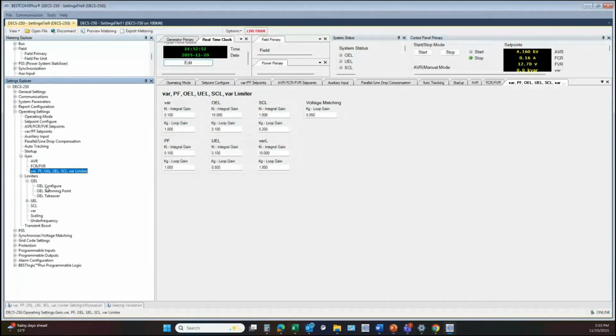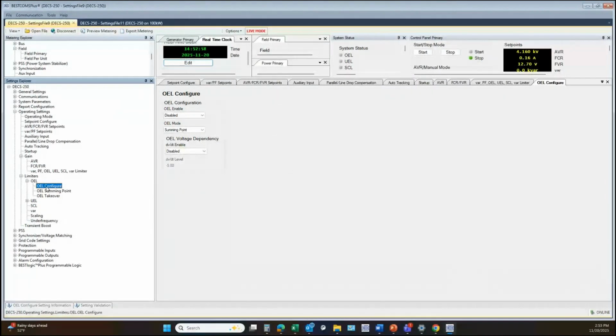Limiters are very important, especially the overexcitation limiter within the DECS. You will not have a better piece of protection in place if the DECS can control excitation directly. Then you should rely upon it to limit excitation instead of relying on an external relay to trip off every time you increase excitation beyond certain levels. So you definitely want your external generator protection relays in place. I'm not trying to say don't have protection, but it's important, since the DECS has direct control over excitation, that you set up these overexcitation limiters.